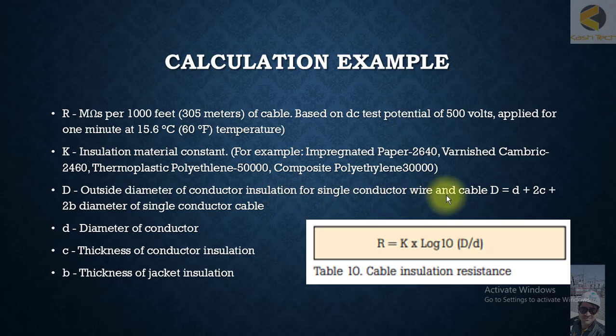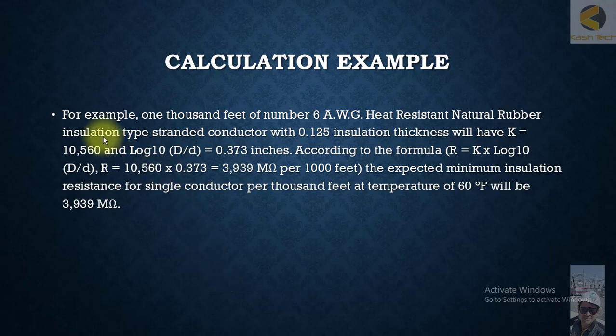D is outside diameter of conductor insulation for single conductor wire and cable. D is equal to d plus 2c plus 2b diameter of the single conductor cable, where small d is diameter of conductor, c is thickness of conductor insulation, b is thickness of jacket insulation.